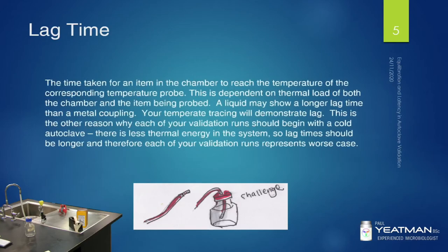So what is the lag time? The lag time is the time taken for an item in the chamber to reach the temperature of the corresponding temperature probe. This is dependent on the thermal load of both the chamber and the item being probed. A liquid may show a longer lag time than a metal coupling, or it may not — your temperature tracing will demonstrate where the lag is. This is the other reason why each validation run should begin with a cold autoclave: there is less thermal energy in the system, so lag time should be longer, and therefore each validation run will represent a worst case.